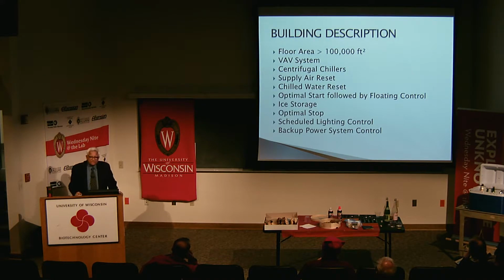Optimal stop. This is a program where you shut off the chiller before the end of occupancy. Say 5 o'clock is the end of occupancy. You may want to shut off the chiller based on the optimization program, maybe at 4:00 p.m. or 3:30 or 4:30, so that you make use of the flywheel effect of the chiller capacity available in the chiller pipe. So this results in chiller energy savings.